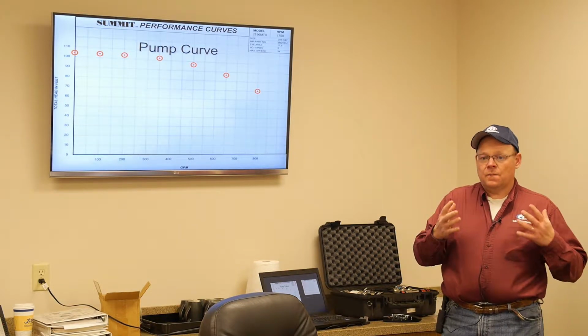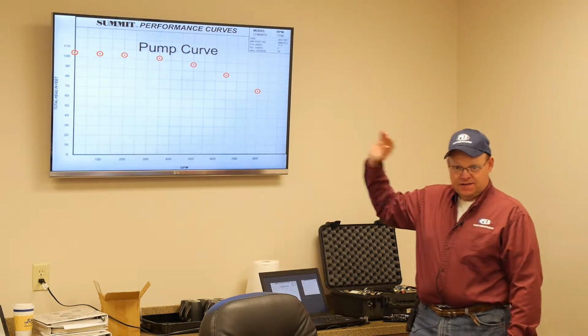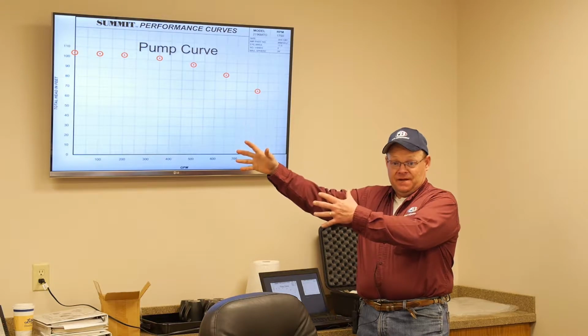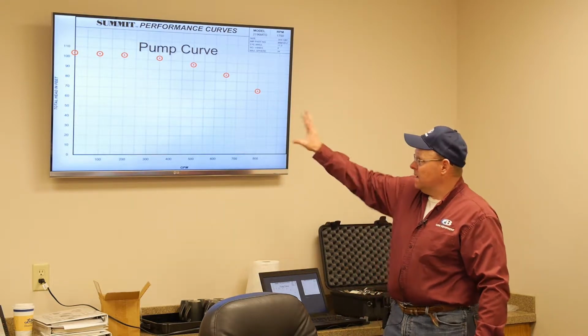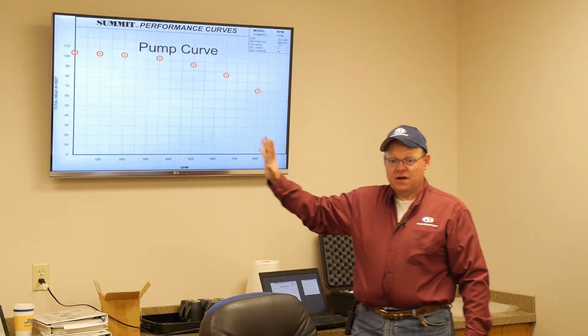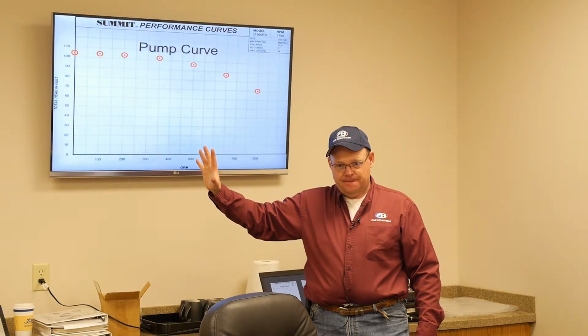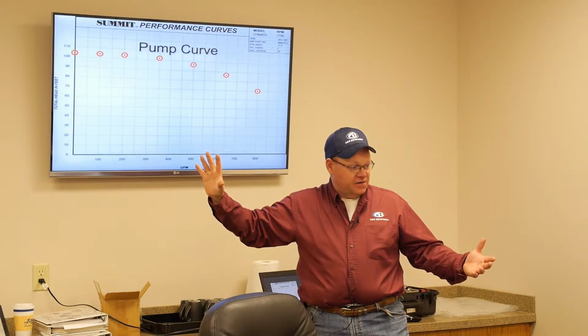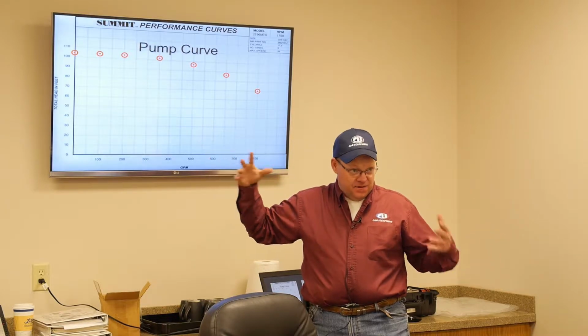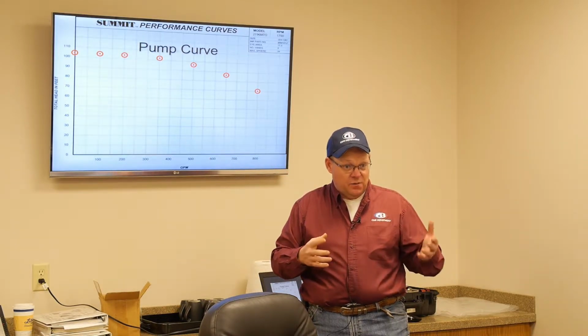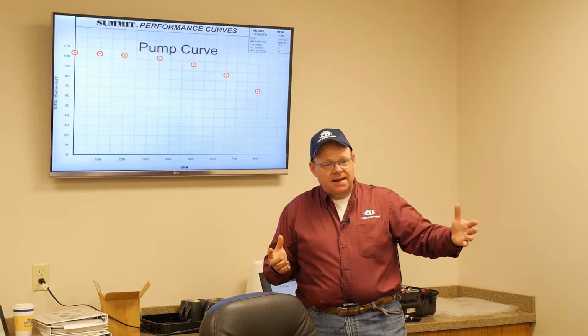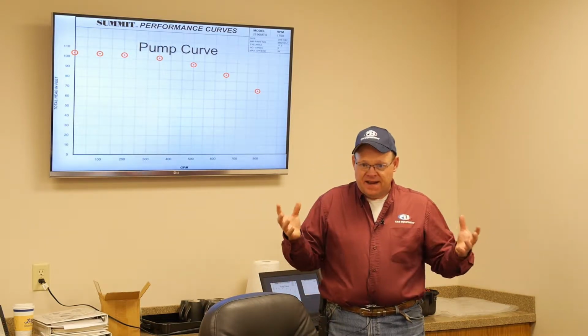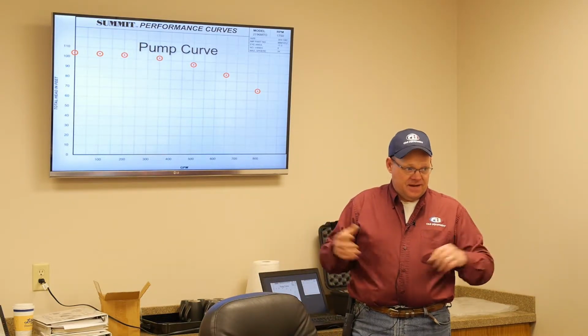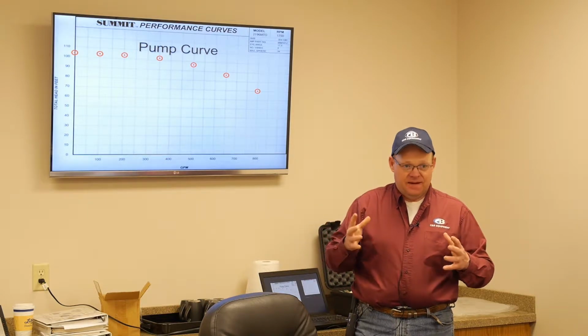We've been talking all morning about having a system that was open to atmosphere. You could have this pump have 500 pounds of suction. Like if we were talking about an NGL, something that has to be compressed to keep it in a liquid state because of its boiling point. Propane, anything that will boil off at atmosphere. If you opened up the tank, it would go to vapor. Anything in that regard. So you could have 500 pounds on the suction side.